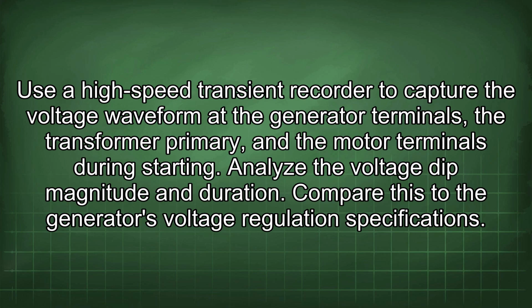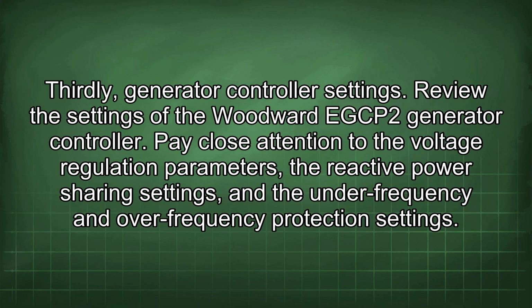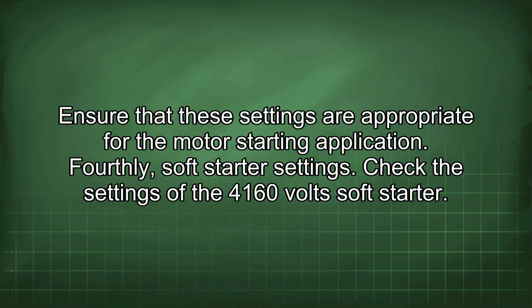Compare this to the generator's voltage regulation specifications. Thirdly, generator controller settings. Review the settings of the Woodward EGCP2 generator controller. Pay close attention to the voltage regulation parameters, the reactive power sharing settings, and the underfrequency and overfrequency protection settings. Ensure that these settings are appropriate for the motor starting application.